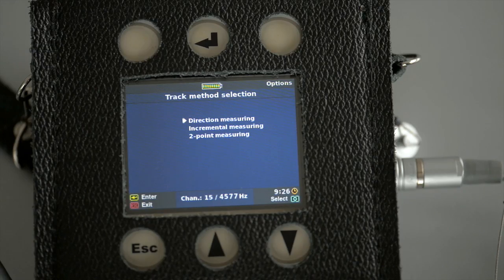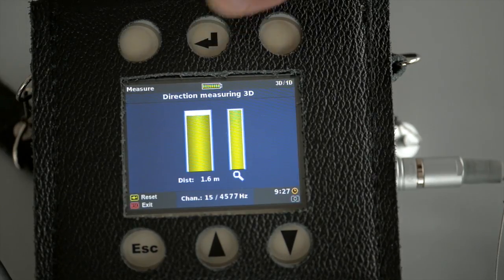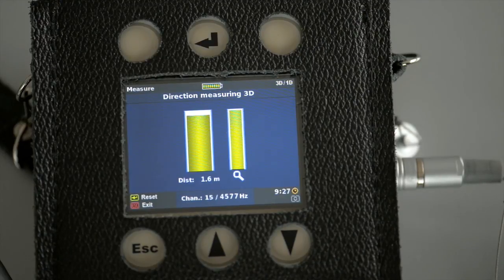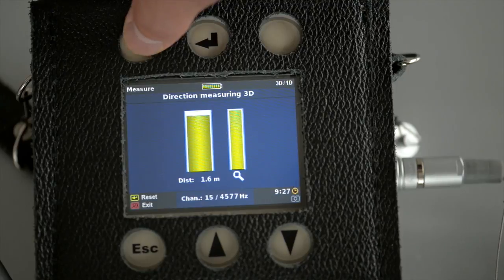We can choose one of the following tracking methods: direction measuring, incremental measuring, and 2-point measuring. The subsequent measurements within these 3 methods are much quicker than the scanning method in the main screen. The selection is done by pressing the up and down keys and accepting it with the Enter key. The direction measuring method was chosen. Now we perform the measurement.